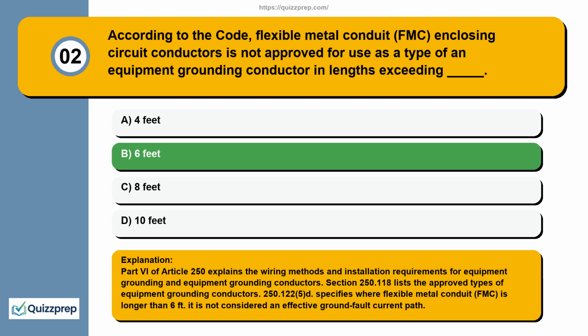Part 6 of Article 250 explains the wiring methods and installation requirements for equipment grounding and equipment grounding conductors. Section 250.118 lists the approved types of equipment grounding conductors. Section 250.122(E) specifies where flexible metal conduit, FMC, is longer than 6 feet, it is not considered an effective ground fault current path.